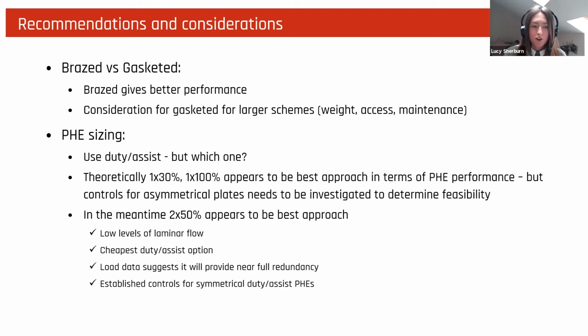Well, it appears that brazed plate heat exchangers give better flow performance overall, but when you have larger schemes, consideration may want to be given for gasketed plate heat exchangers, just because gasketed can be assembled in a plant room or disassembled and reassembled pretty easily. So if you've got a really heavy unit and your access isn't great, gasketed might be an easier solution because you avoid the need to lift heavy things and can get through access a bit easier.